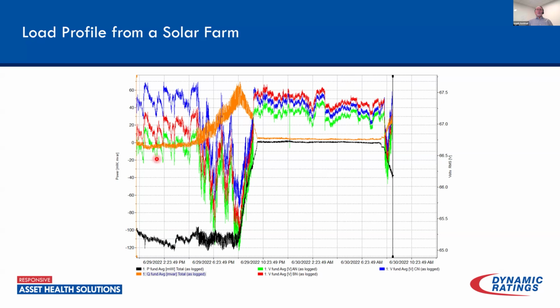And you can see for the most part, on the left-hand side here, they fluctuate a little bit, but they're pretty steady state, and they at least are moving as a group. What I think is interesting is the period where we're generating about 100, 110 megawatts. This is the VAR flow coming from the inverters at that point in time.